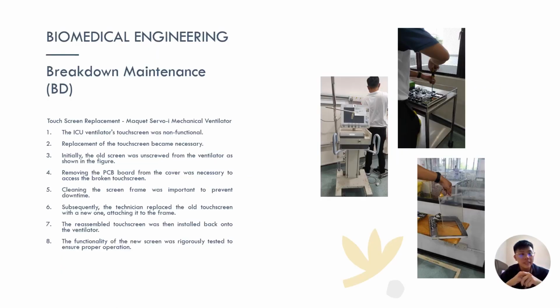So for breakdown maintenance, I have attended two breakdown maintenance cases. The first is the touchscreen replacement on a Servo-i mechanical ventilator. During the breakdown maintenance, we found that the touchscreen was not functional. That's why it was necessary to replace the touchscreen.